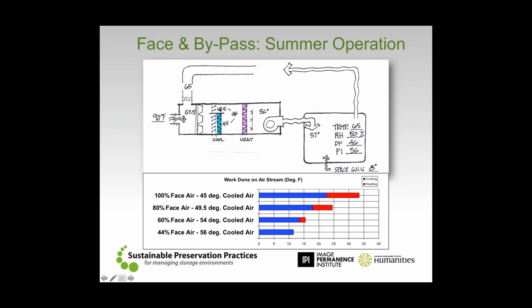But notice as we start bypassing some of this air and changing these blends, that means now that if we only send 80% of that air over the face of the cooling coil, this blending condition on the other side between that 45 degrees, 80% of that, and 20% of 67.5 degrees, that means this mixed air, this cooled condition blended, is going to wind up at 49.5 degrees. We get the same condition out in the space, but it reduces the amount of cooling we have to do, and it also reduces the amount of reheat that we have to do. And we can keep taking this further and further. In terms of energy savings or practicality, we may choose to stop here or stop here in real life.